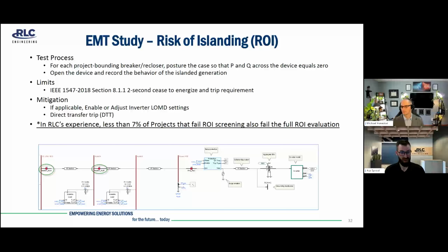Our second mitigation strategy, the one most of you are likely familiar with, is direct transfer trip, or DTT. Now, I would say you could go through this full EMT study and ROI process and still require DTT. But in our opinion, it's a lot better to run the full study rather than requiring this by default or based on the outcome of a screen. And to add to that, some statistics, based on what we've studied, all the projects we've studied, only 7% of projects that failed the screen resulted in failures upon the full EMT ROI evaluation. So a 93% pass rate is pretty good, in my opinion.